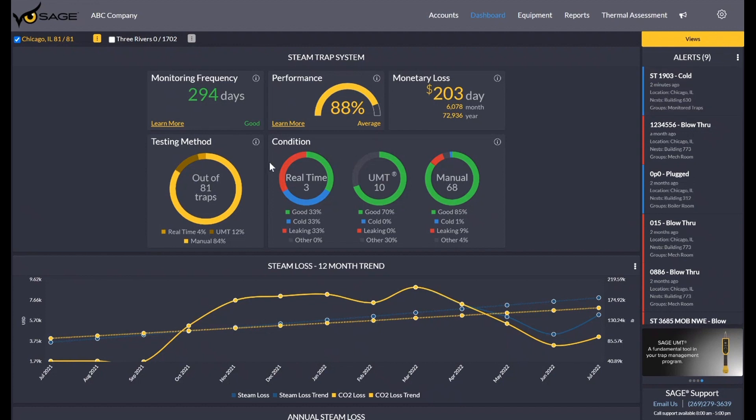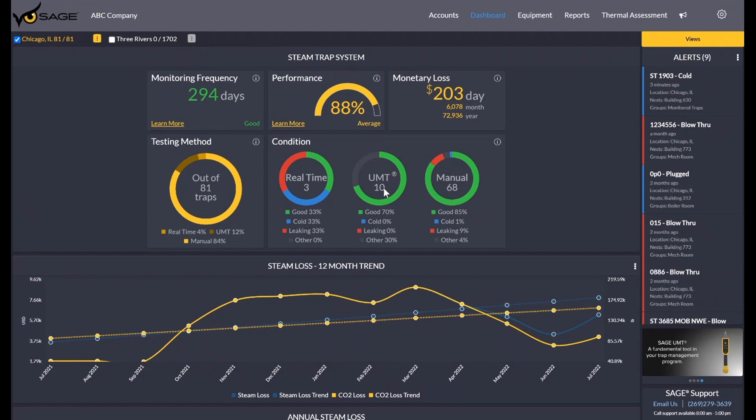You can also see we have the condition breakdown right here, and again, it's going to break it out by the three ways you can collect data in Sage. You have our real-time monitors, a device that actually clamps on to the piping or the trap itself to monitor it 24-7. Our handheld Sage UMT that you can use to test the trap. And then, of course, you can manually update the condition after surveying it a different method. You can update it through the web here or through the mobile app, and those recordings will be documented here.